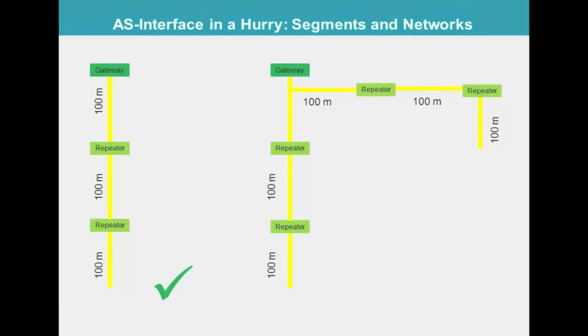Using this approach, it is possible to set up a five-segment network with 500 meter length. Note that the gateway now sits in the middle of the network. The underlying rule is that no module must be more than two repeaters from the gateway.